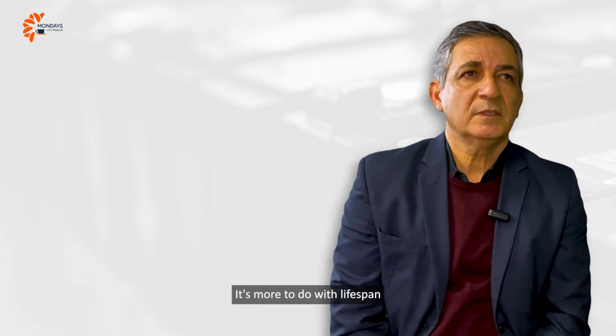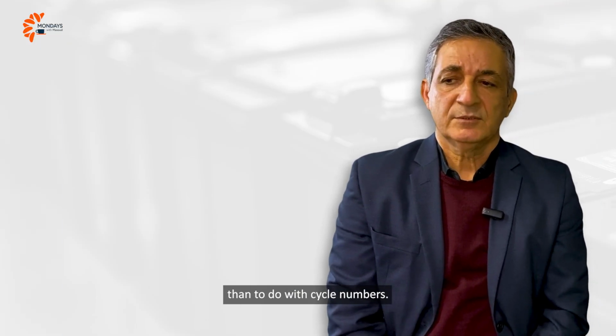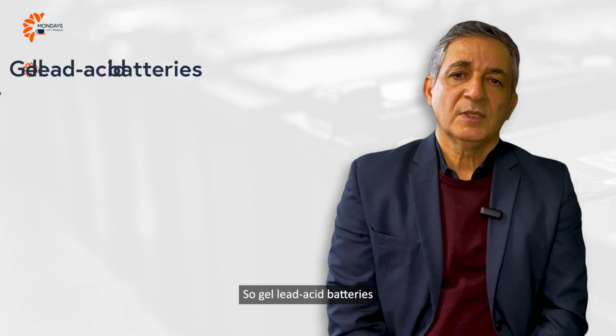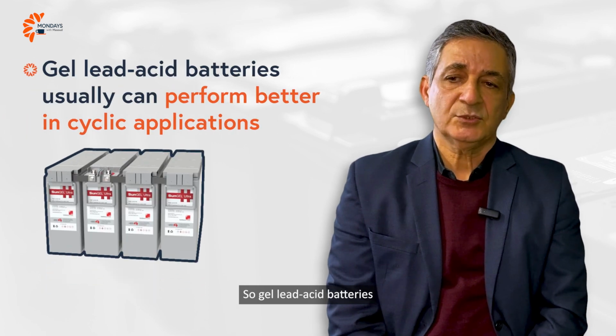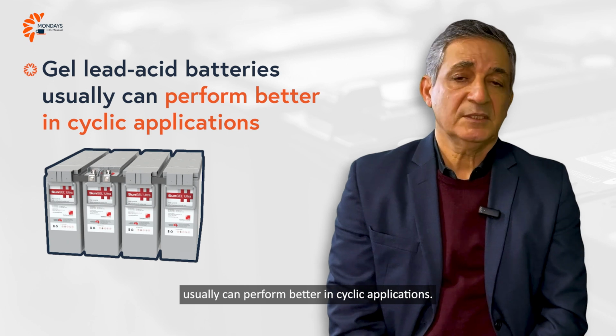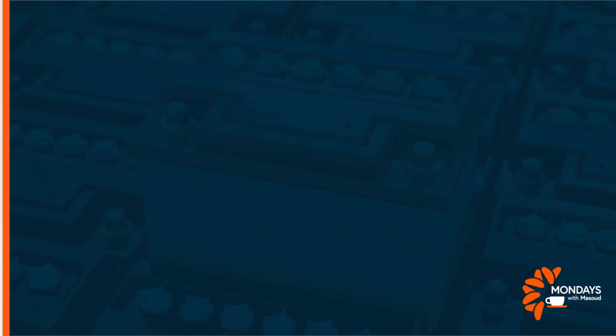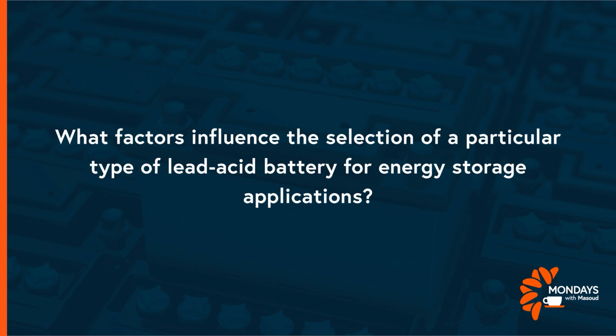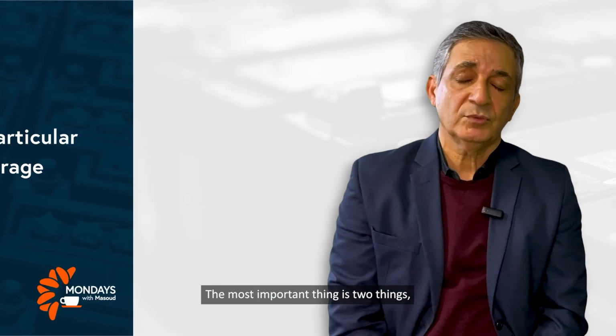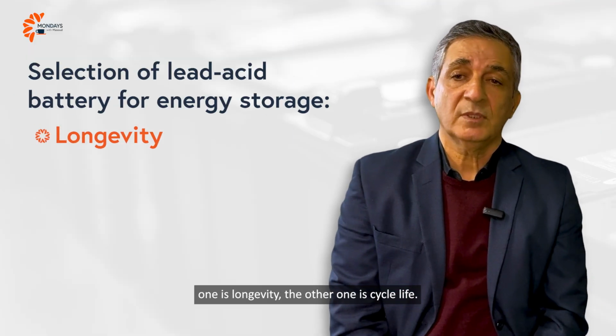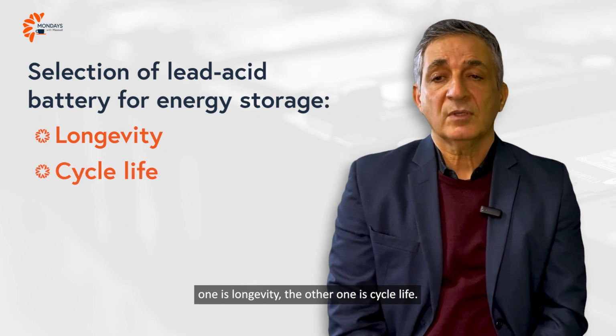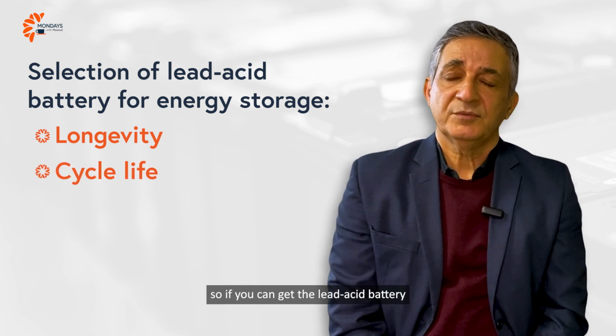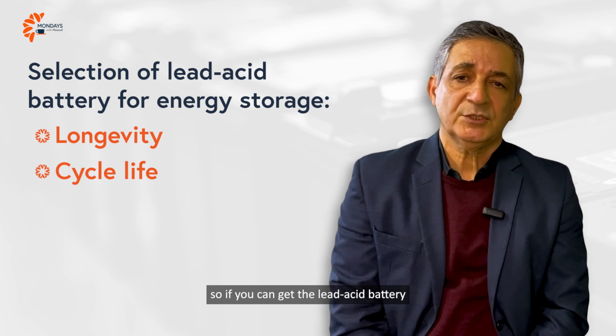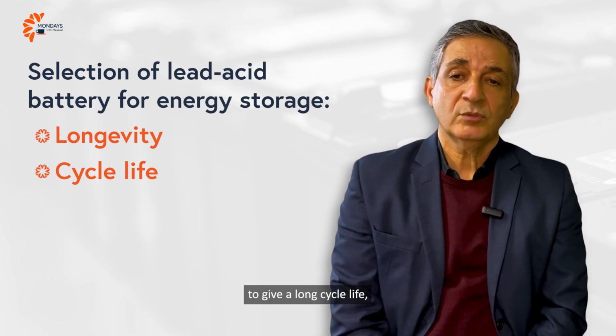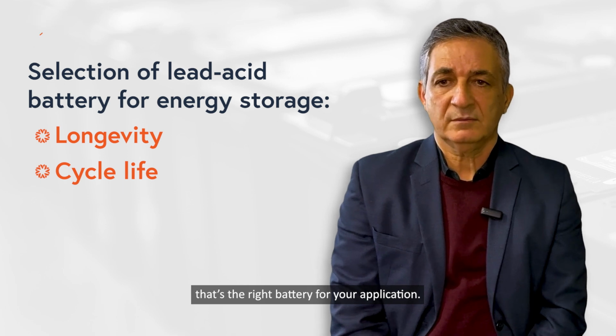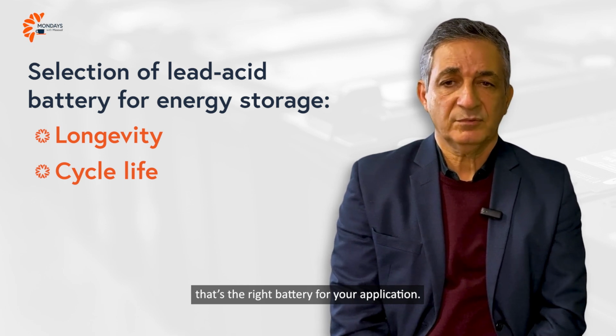It's more to do with lifespan, to do with cycle numbers. So gel lead acid batteries usually can perform better in cyclic applications. The most important thing is two things: one is longevity, the other one is the cycle life. So if you can get a lead acid battery to give long cycle life, that's the right battery for your application.